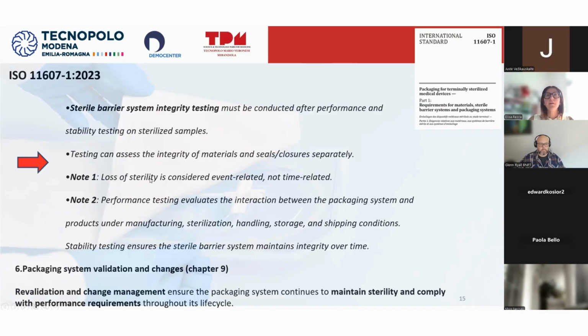Note 1: loss of sterility is considered event-related, not time-related. Note 2: the performance testing evaluates the interaction between the packaging system and the products under manufacturing, sterilization, handling, and storage, as well as shipping conditions. So stability testing ensures that the sterile barrier system maintains integrity over time.